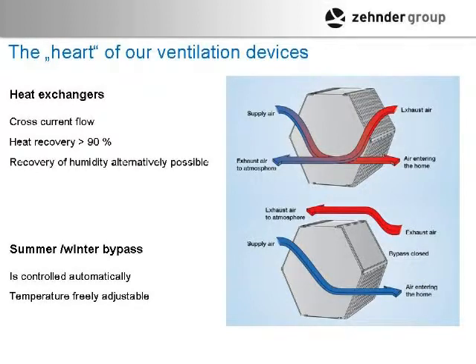When the sun goes down and outside gets cool, you may want to actually cool your house, and we have a summer bypass where the exterior air is coming into the house, can come straight through the box because the outgoing air is diverted around the core. Instead of going through the core here and transferring heat, that air is just directed straight out of the house. So actually that cool night air can come in and cool your house out.